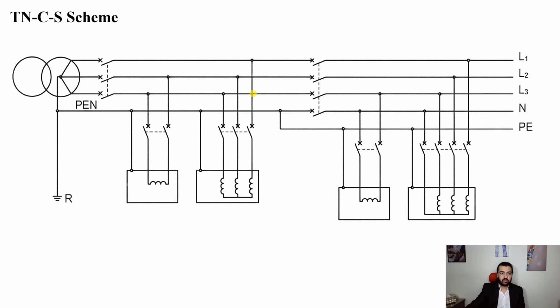So here the system looks like this. We have the supply side and we have the load side. What we can do is start as TN-C. You can see phase 1, phase 2, phase 3, and the neutral, which acts as PEN, protective earth and neutral at the same time. So we have TN-C 4-wire until we get to a large building, for example, like this building.